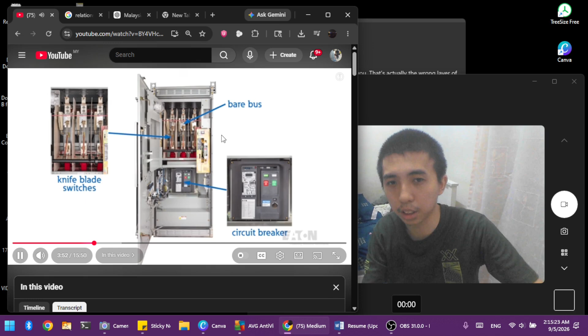There are two types of overcurrent and fault protection available in metal enclosed products. Power fuses that can be current limiting or non-current limiting, or circuit breakers with either a trip unit like our VCPT breaker or with a protective relay typical of most medium voltage gear. There are pros and cons to consider when choosing between using a power fuse or circuit breaker in your metal enclosed equipment. Let's review some of the items you need to consider.